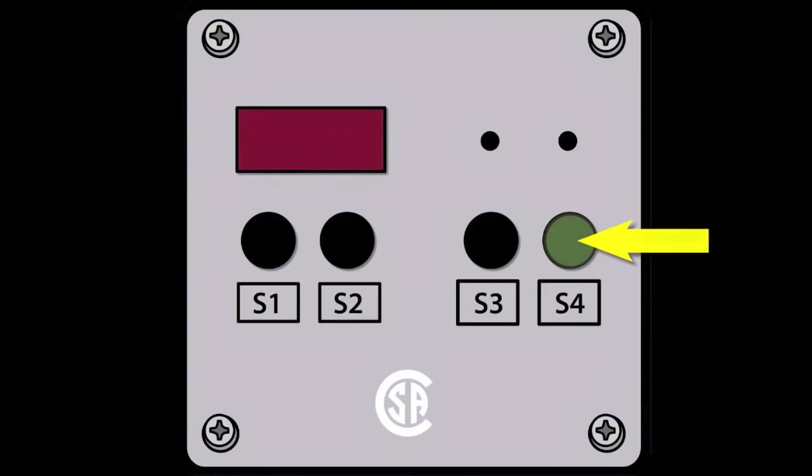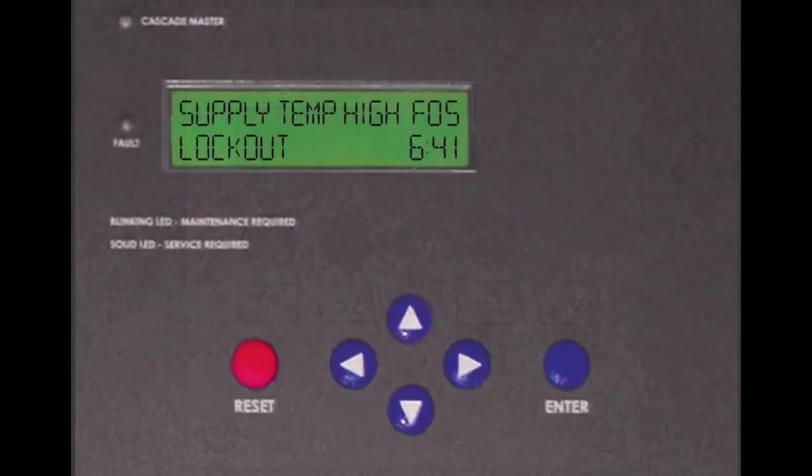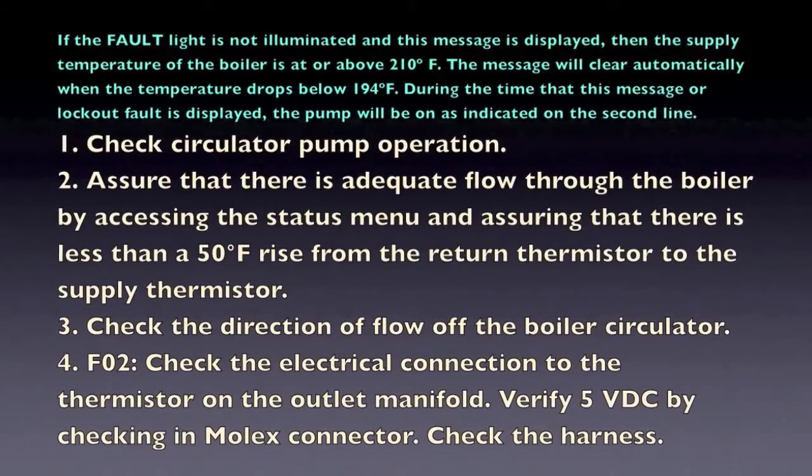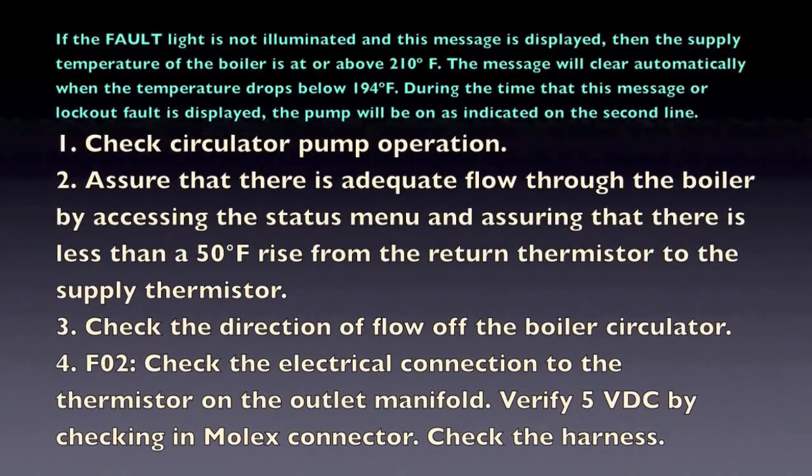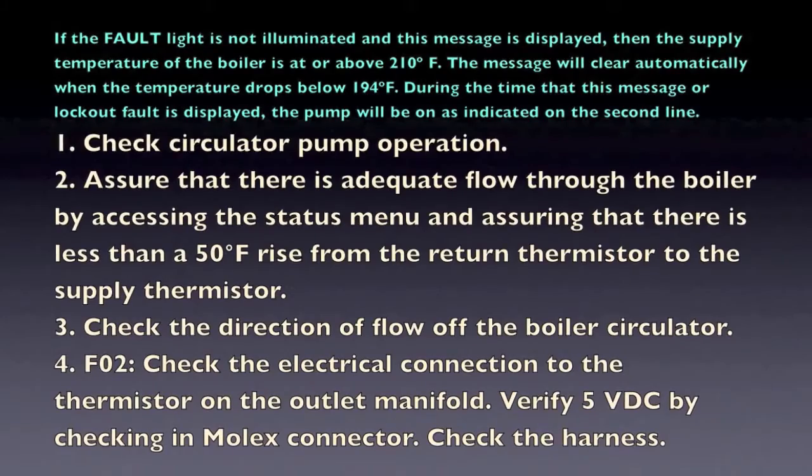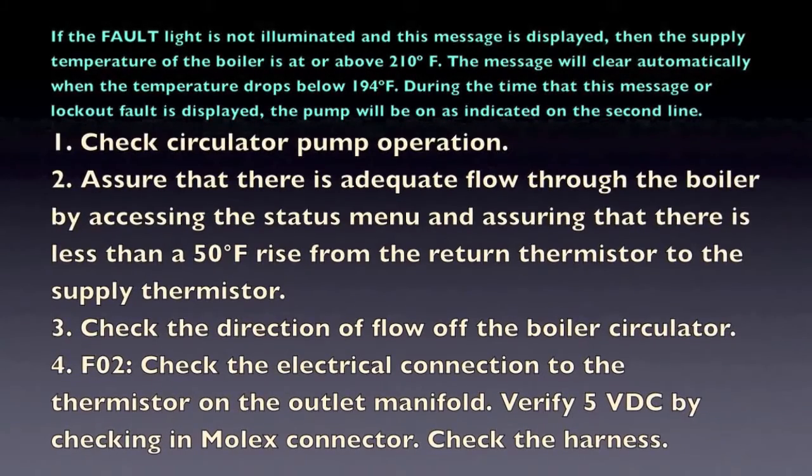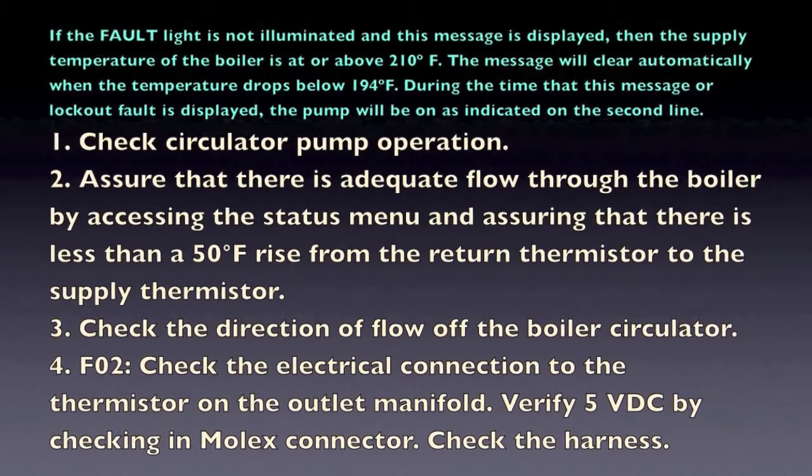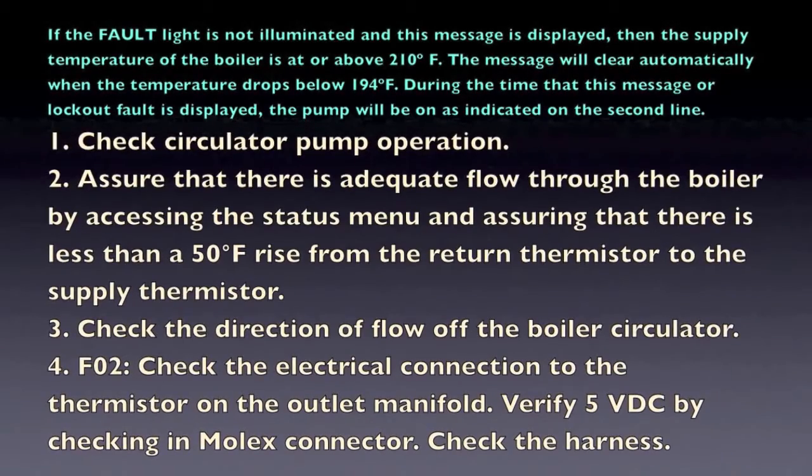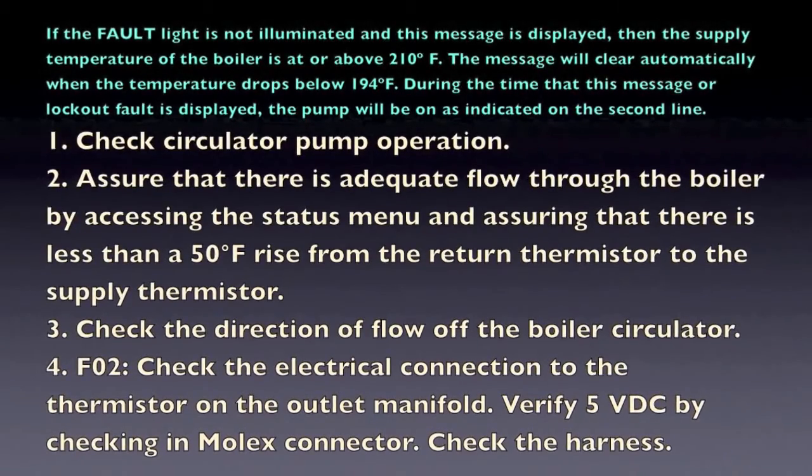If the fault light is not illuminated and the message is displayed, then the supply temperature of the boiler is at or above 210 degrees F. The message will clear automatically when the temperature drops below 194 degrees F. During the time that this message or the lockout fault is displayed, the pump will be on as indicated on the second line.